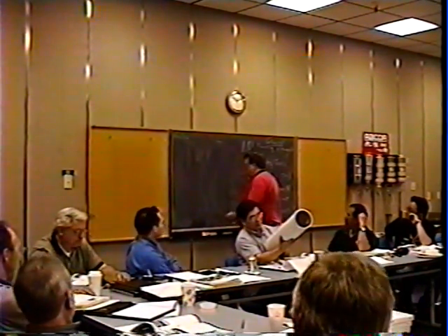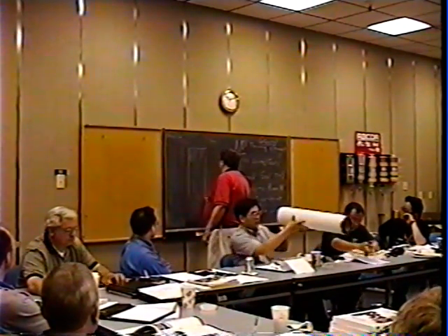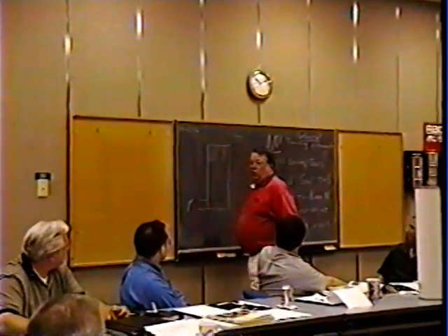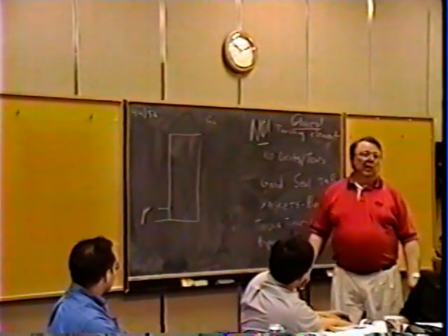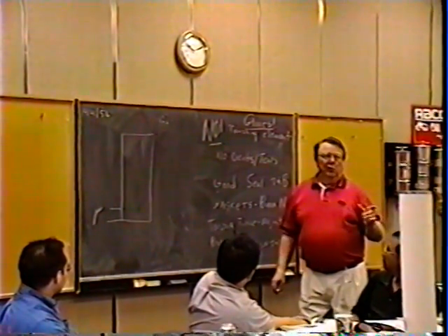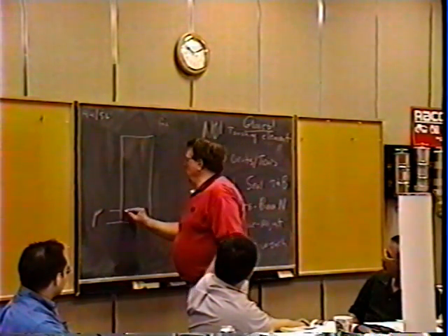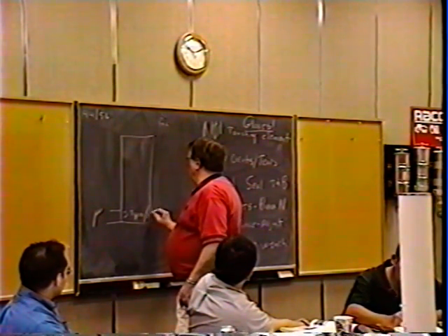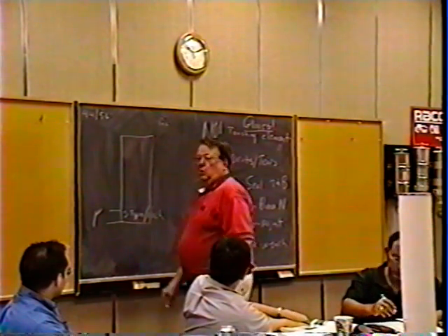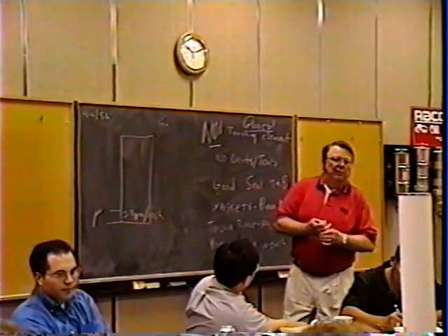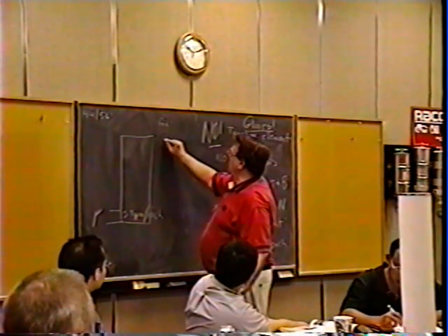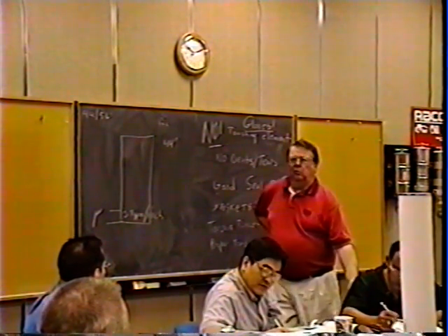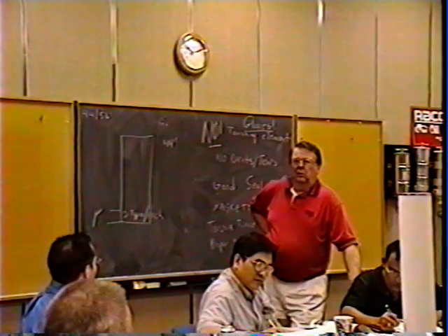Okay, coalescer. One inch. This is where you find out how good people's coalescers are. The industry average is 2.7 GPM per inch. Anybody have a calculator? If I have a 44-inch coalescer, how many gallons can that flow? 120? 109? Just under 119.